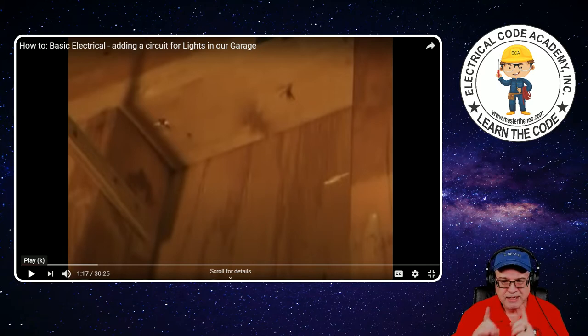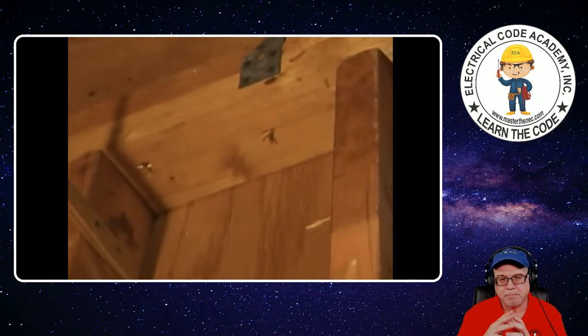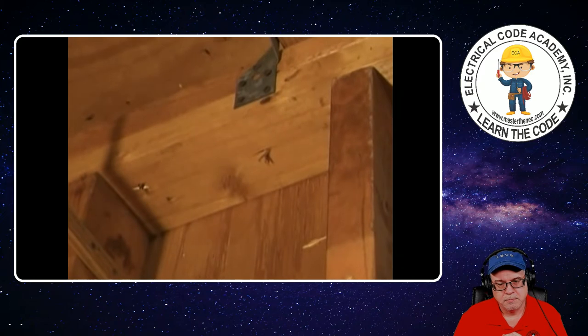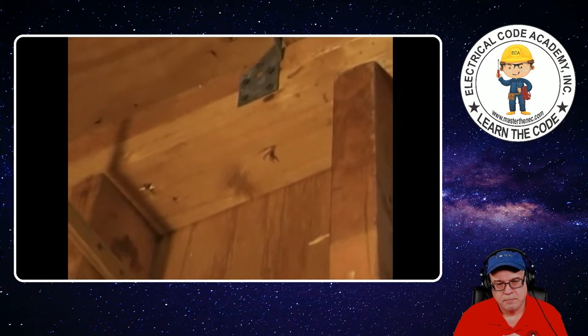In 300.4, you'll have subsections A, B, C, and D with different requirements depending on whether it's bored holes, metal studs, or parallel with framing members. All those rules are there — check it out — because you do have to protect those cables as they go through bored holes or parallel with framing members. All are going to be wrapped around that inch-and-a-quarter dimension. Through the double top plate, we're going to drill a hole close to the center of the two-by-fours.